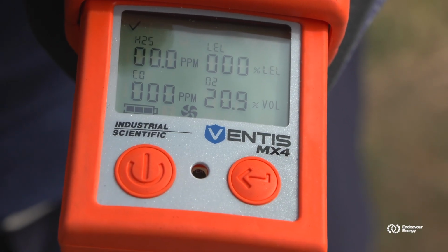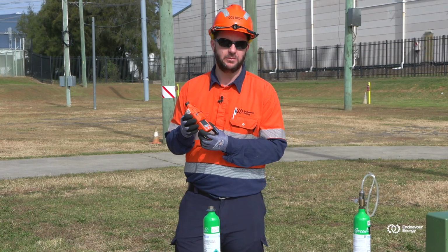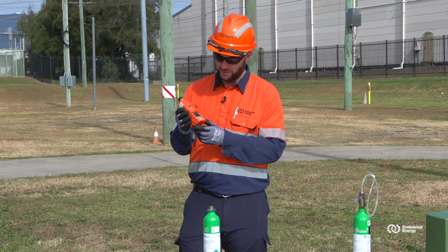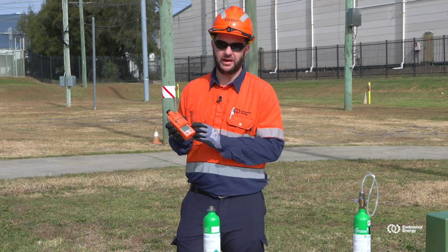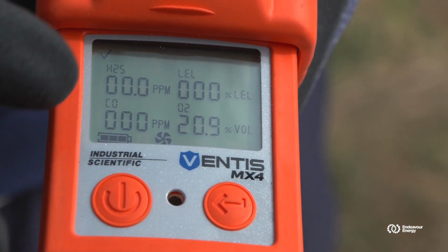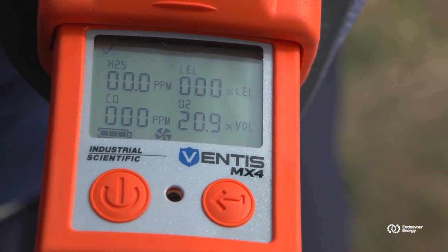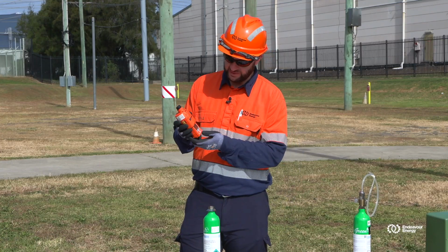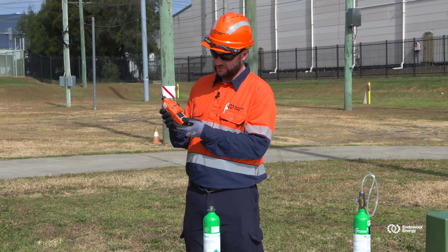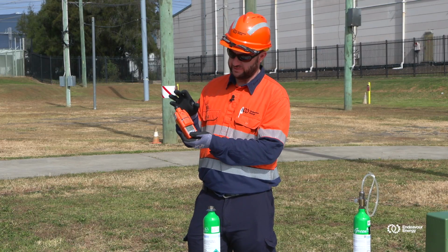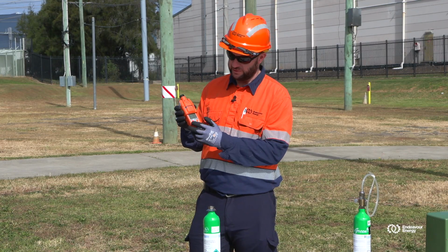The H2S and the carbon monoxide are measured in ppm, which is parts per million. The lower explosive limit and the oxygen levels are measured in a percentage. When we're using the gas detector now, we're going to have to zero it. So we're going to scroll through the menus here on the gas detector.